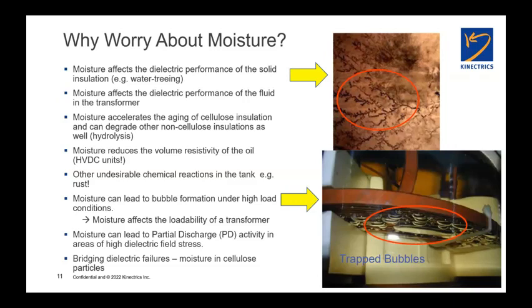As you probably know, these days there are many alternative fluids that can be used, and each of those reacts somewhat differently to moisture, but fundamentally the same issues are prevalent. But I'm going to be talking specifically about mineral oil filled transformers. One of the things that's not obvious, but to me is one of the most important factors, is that moisture acts as an accelerator of the aging of the cellulose insulation inside the unit.